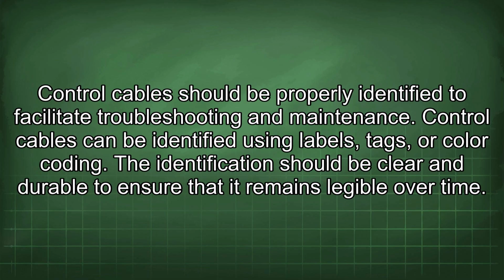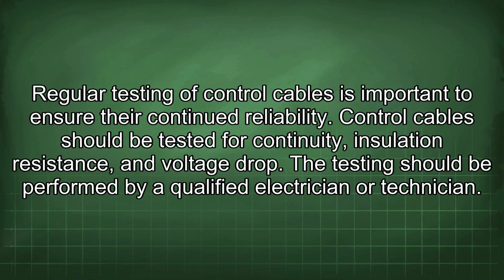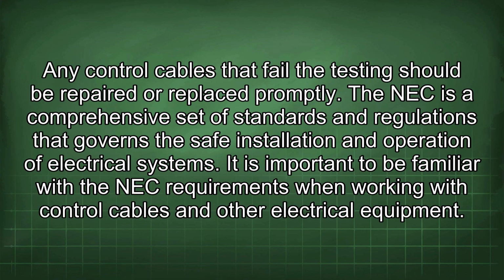Control cables should be properly identified to facilitate troubleshooting and maintenance. Control cables can be identified using labels, tags, or color coding. The identification should be clear and durable to ensure that it remains legible over time. Regular testing of control cables is important to ensure their continued reliability. Control cables should be tested for continuity, insulation resistance, and voltage drop. The testing should be performed by a qualified electrician or technician. Any control cables that fail the testing should be repaired or replaced promptly.